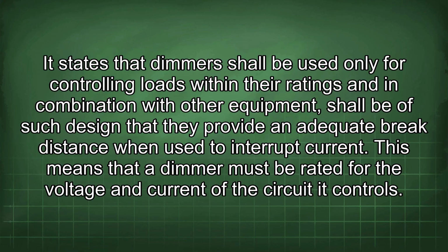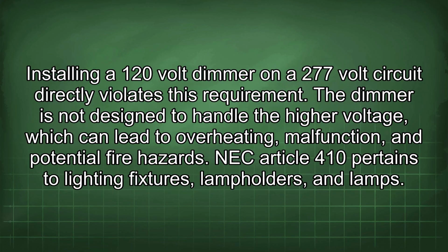This means that a dimmer must be rated for the voltage and current of the circuit it controls. Installing a 120-volt dimmer on a 277-volt circuit directly violates this requirement. The dimmer is not designed to handle the higher voltage, which can lead to overheating, malfunction, and potential fire hazards.